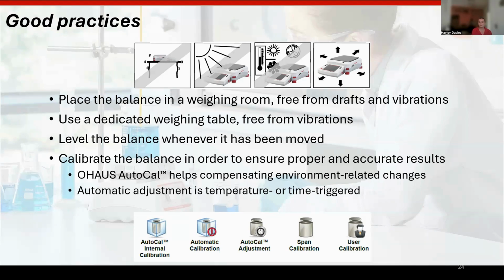Just a quick one, Hayley, sorry, while you're on vibrations, there's a message come in from Claire. What about the vibration in a fume cupboard? Good question. Fume cupboards are a tricky one, although not impossible. On certain balances, you have a filter level. What you can do to mitigate the vibrations and the airflow in a fume hood is adjust the filter level. That basically means you can tell the balance not to change the reading on the screen until it gets to 3 or 4 decimal places, depending on the type of balance.